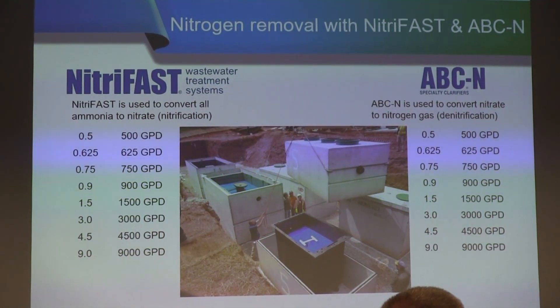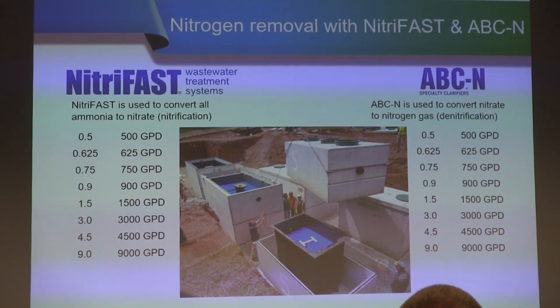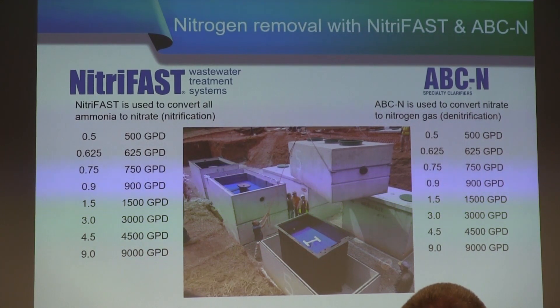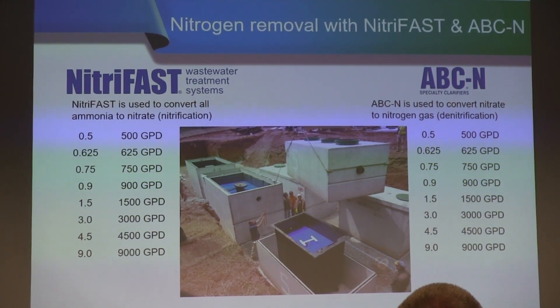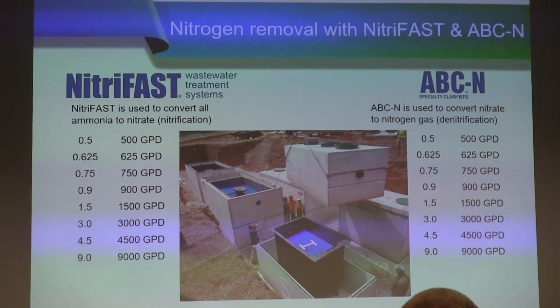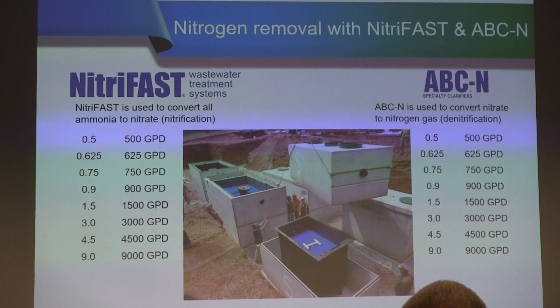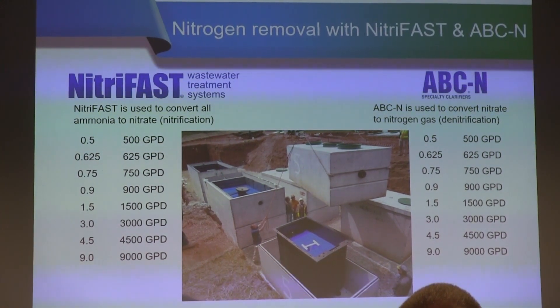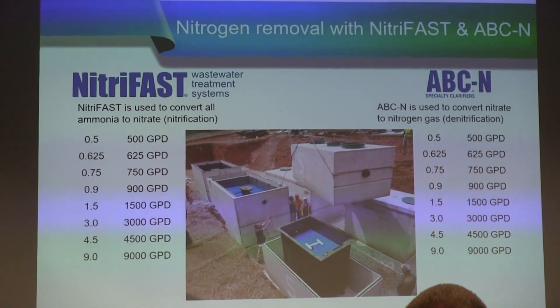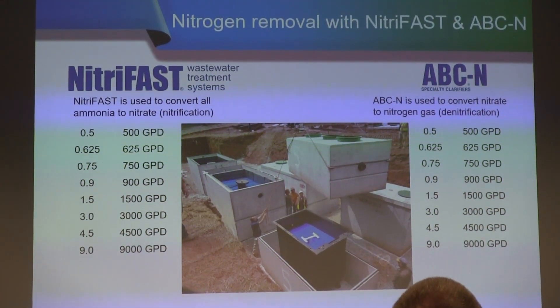Just know that nitrogen removal has a part one and a part two process. NitriFAST completes part one, and then the ABCN does part two — what's called denitrification. That's what actually takes nitrogen out of the water by biologically converting that nitrogen to a gas, which then leaves through the vents.